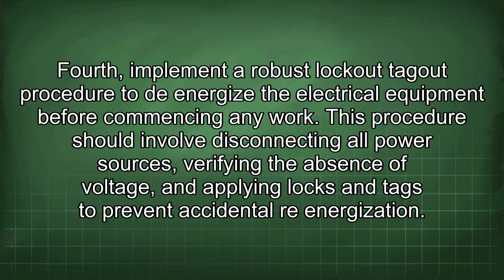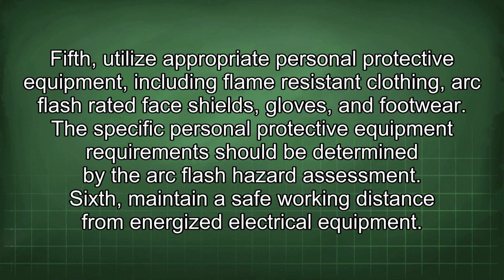Fourth, implement a robust lockout-tagout procedure to de-energize the electrical equipment before commencing any work. This procedure should involve disconnecting all power sources, verifying the absence of voltage, and applying locks and tags to prevent accidental re-energization. Fifth, utilize appropriate personal protective equipment, including flame-resistant clothing, arc flash-rated face shields, gloves, and footwear. The specific personal protective equipment requirements should be determined by the arc flash hazard assessment.